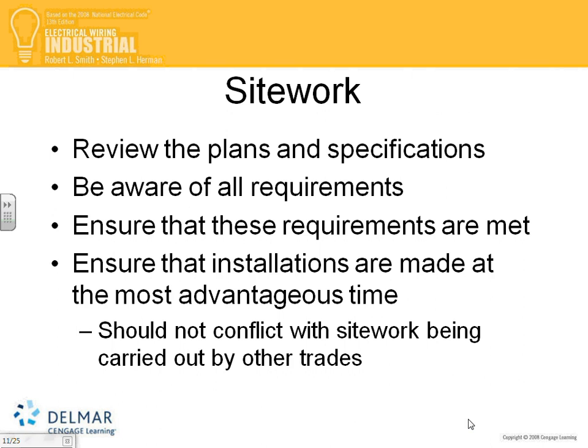Requirements are met for the site plan, guys — review the plans and specifications from an electrical contractor's point of view. Be aware of whatever special requirements they have, and ensure that these requirements are met. Your work should not conflict with the site plan being carried out by other trades. As an electrical contractor, you can get into a lot of trouble if you don't know what the site plan is, especially with digging — trenches, especially if you're going outside: parking lot trenches, parking lot light trenches, site lighting, power coming into the building, and generators if you want to install generators. When the generator comes in, guys, certain cities measure the noise of the generators from the property line. So if someone decided they want a generator and you think, no problem, we'll just put it in the back of the building — well, have you paid attention to the easement and to the property line?